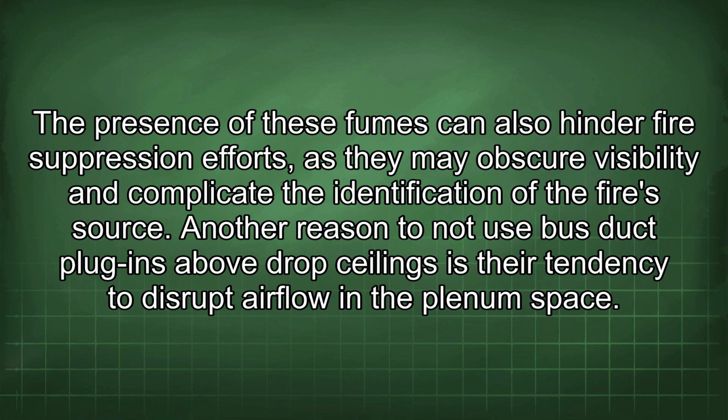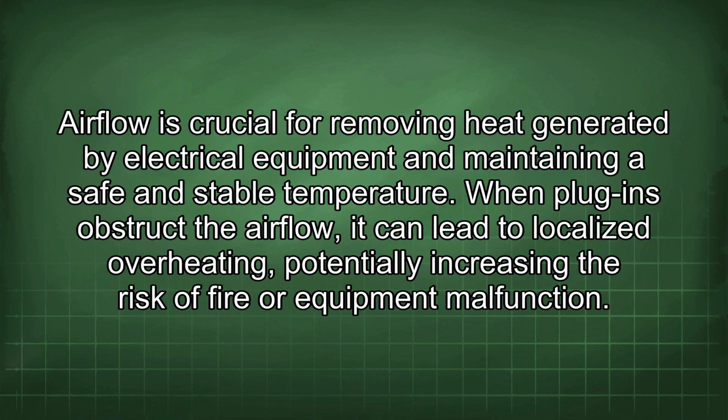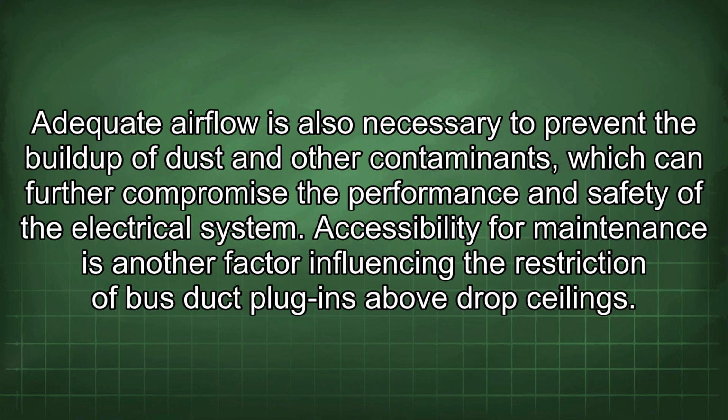Another reason to not use bus duct plug-ins above drop ceilings is their tendency to disrupt airflow in the plenum space. Airflow is crucial for removing heat generated by electrical equipment and maintaining a safe and stable temperature. When plug-ins obstruct the airflow, it can lead to localized overheating, potentially increasing the risk of fire or equipment malfunction. Adequate airflow is also necessary to prevent the buildup of dust and other contaminants, which can further compromise the performance and safety of the electrical system.